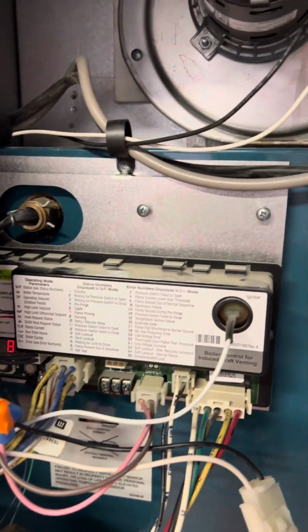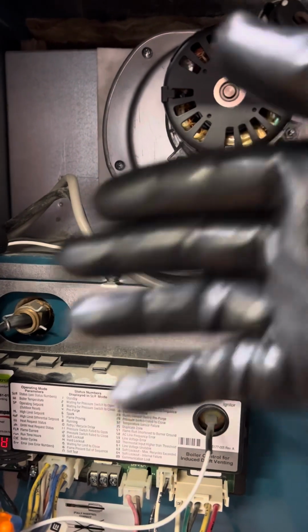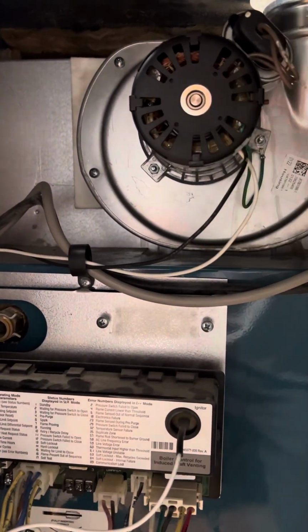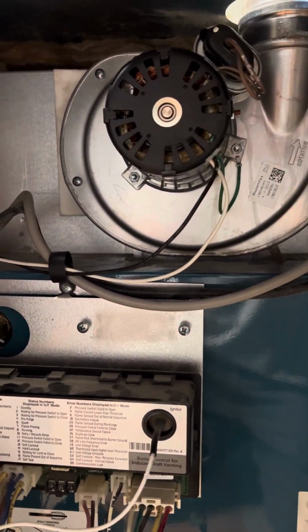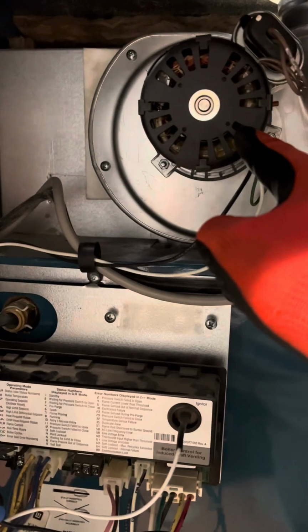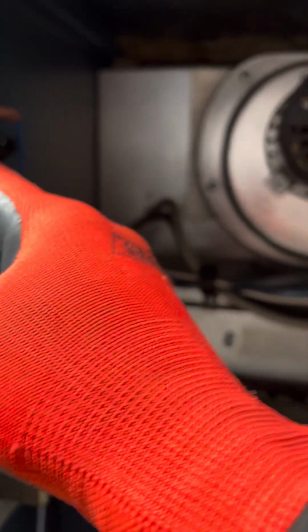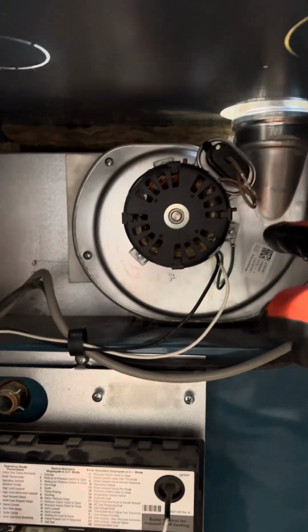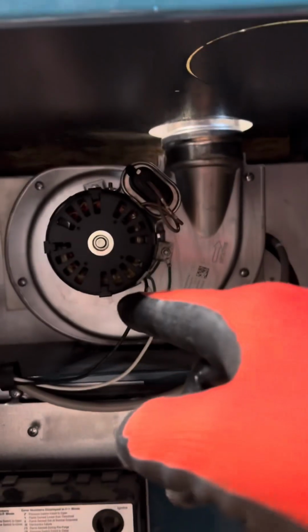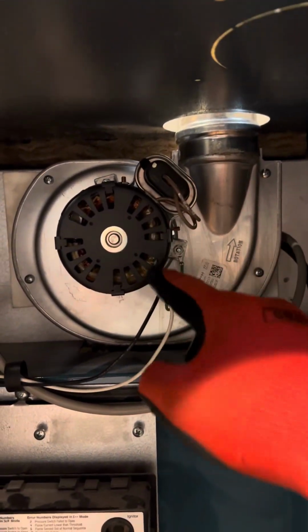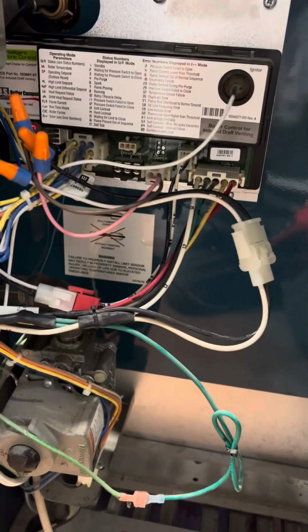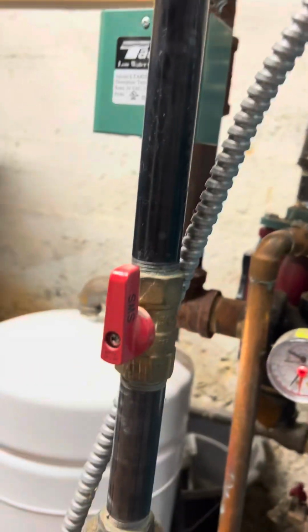All right? Your inducer motor here, that sucks out any gases, that's the pre-purge. All right? This closing, because this creates a vacuum, is going to continue that. It's going to prove that this is working fine. Then there's nothing blocking the flue. All right, because that can happen too. Or if this is broken. All right, after that happens, then the spark, then you have to prove the flame down here. Once that's good, we know that we're not just dumping raw gas into our house, then the flame kicks on.